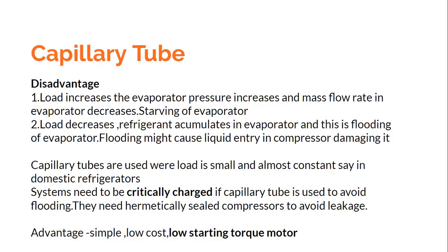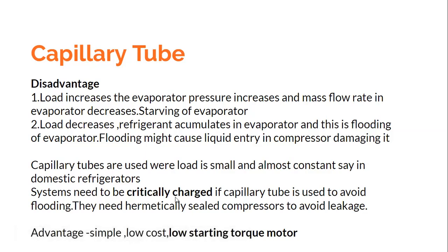So critically charged means the volume of the evaporator is such that it can hold the required amount of charge even when the entire amount of refrigerant gets into the evaporator. That is called critically charged. So this is the most important. That is why I highlighted it. It has to be critically charged. If you don't charge critically, if you charge more, then there would be flooding, and that might damage the compressor.